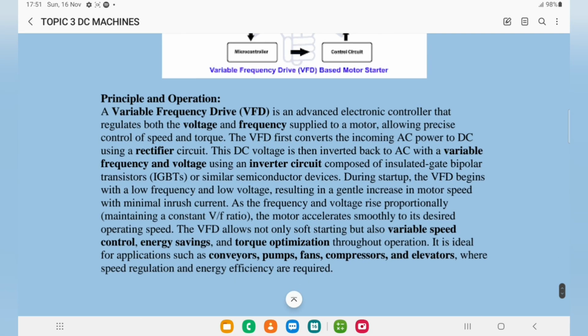During startup, the VFD begins with a low frequency and a low voltage, resulting in a gentle increase in motor speed with minimal inrush current. The frequency and voltage rise proportionally, maintaining a constant V over F ratio, that is, a voltage over frequency ratio. So the motor will accelerate smoothly to its desired operating speed.